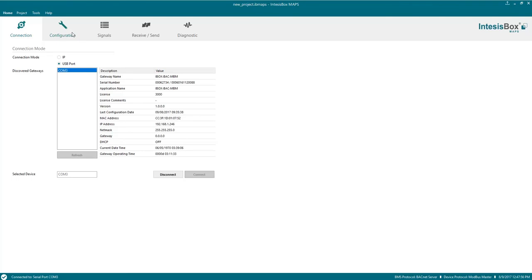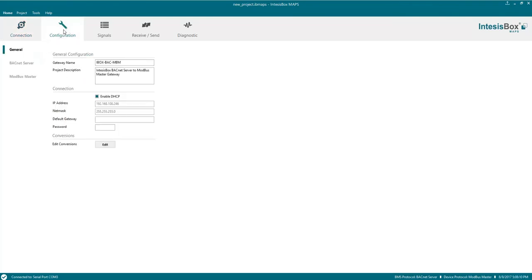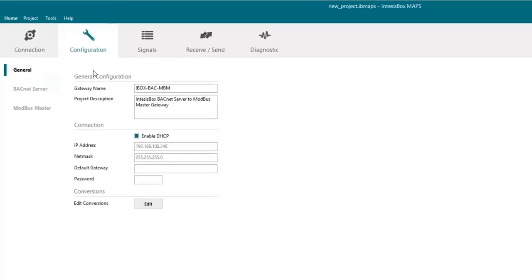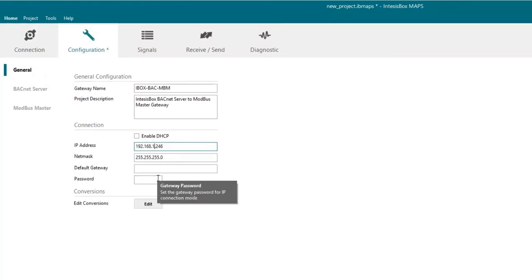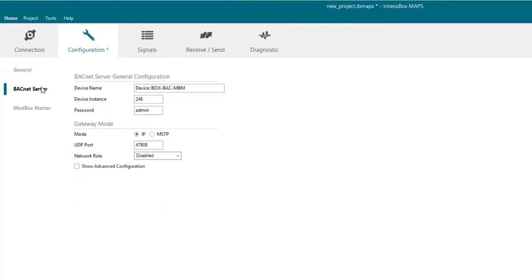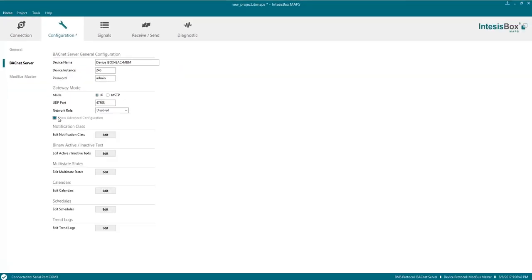So now we are connected and let's begin with the configuration by clicking on the configuration tab. In general settings we will disable the DHCP option as we would like to use a fixed IP. So let's choose the IP and then we will also choose a password for this project and that will be demo. On the BACnet server settings we could change few options including some advanced configuration parameters. But in this case we are not going to modify anything. So let's move to the Modbus settings.